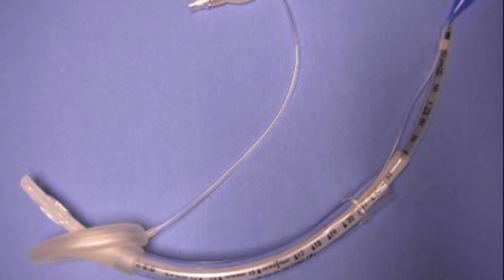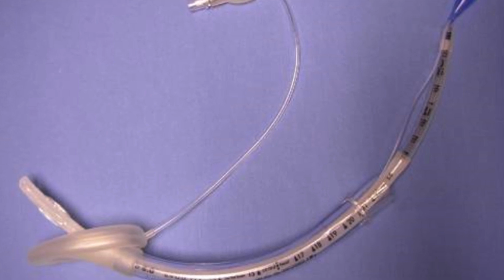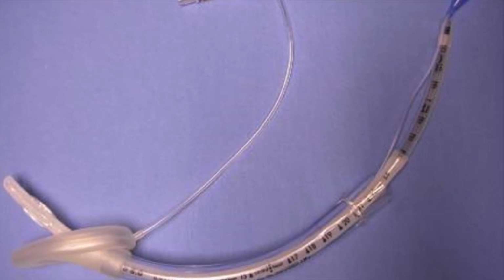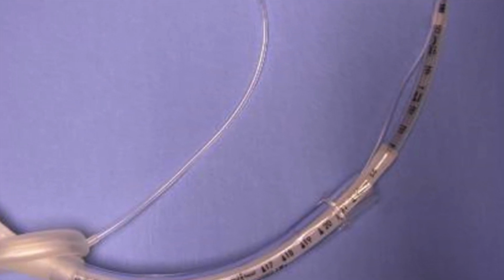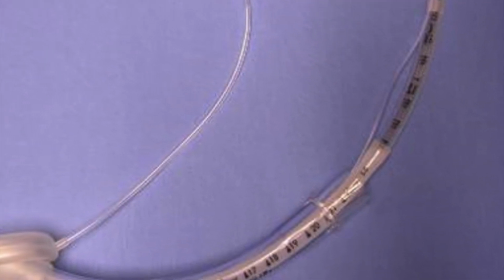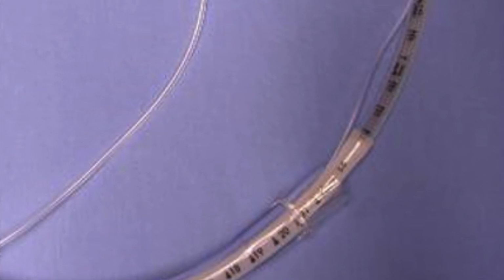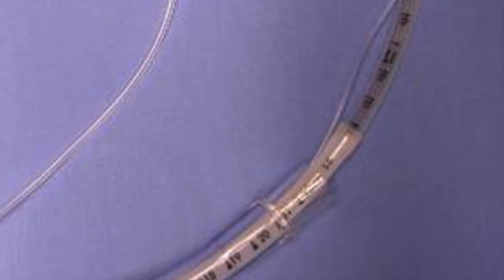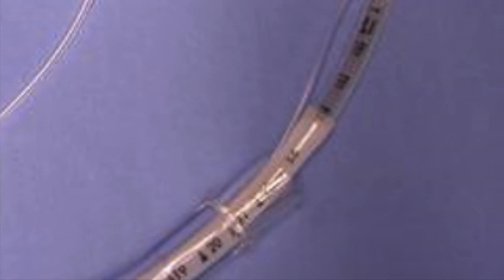the fibroscope. During the manufacturing process of the tracheal tube, the placement of the 15mm circuit connector onto the tracheal tube results in dilating that small section, permitting a same-size tracheal tube to be inserted. Discarding the Murphy's eye portion of the stabilizing tube permits the two-tube junction to remain cylindrical.